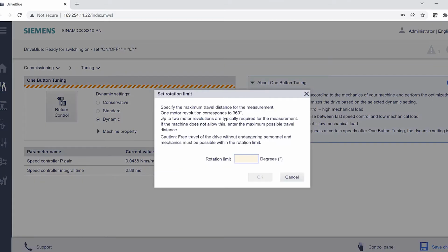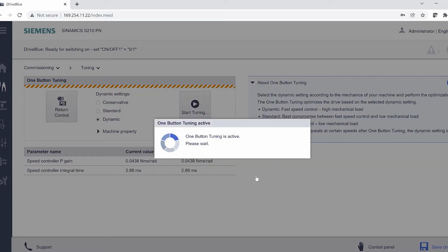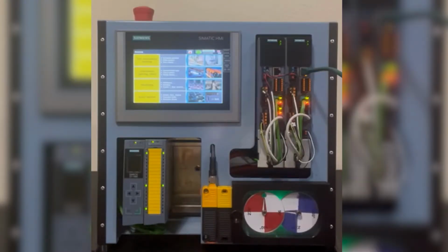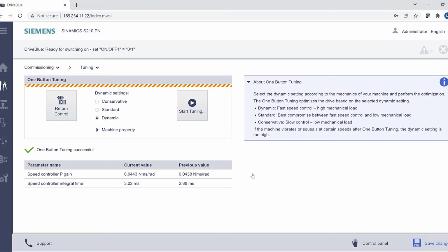When you select Startup, a notice will pop up to tell you that the motor shaft wants to spin during this tune, and it needs to know how much it's allowed to do so within your system. If your motor cannot support a full rotation, enter the maximum degrees of rotation that are allowed. If your motor can spin freely, enter at least 720 degrees, as 2 full rotations are recommended for optimum results. You will see the motor shaft spin at different speeds and directions while the tune is performed.